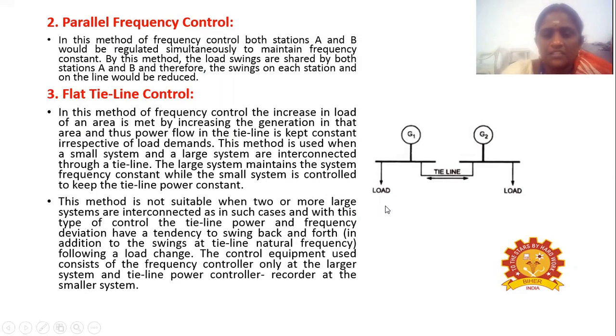In this method, wherever the load demand changes, either at station A or station B, both generators are regulated simultaneously. By this method, the load swings are shared by stations A and B, and therefore the swing on each station and on the line will be reduced. This is called parallel frequency control. Next method is the flat tie line control.